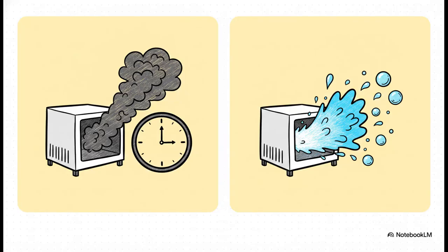But, as you can probably guess, not everything can survive being blasted with superheated high-pressure steam. For those heat-sensitive medical devices, the industry historically had to rely on ethylene oxide, or EO gas. But EO comes with a massive drawback. It's highly toxic. We're talking real cancer risks for workers and surrounding communities. Plus, it requires these painfully long aeration times just to make sure all that toxic gas is fully removed from the product. Fortunately, today we're seeing a huge paradigm shift toward hydrogen peroxide gas plasma. It's highly effective, but so much safer, because once the sterilization cycle is done, the gas literally just breaks down into harmless water vapor and oxygen. Talk about a game changer.